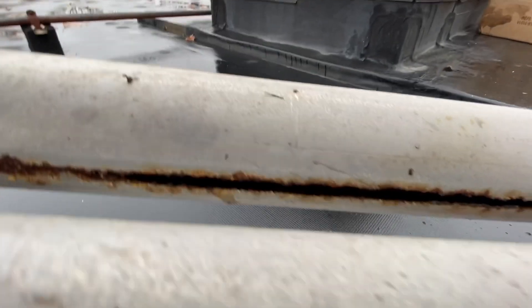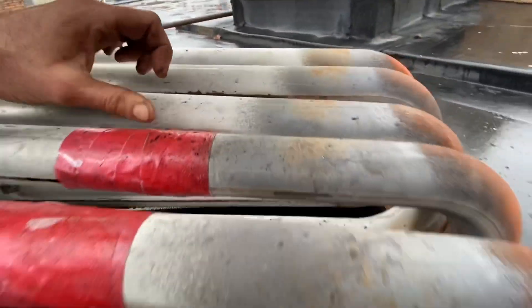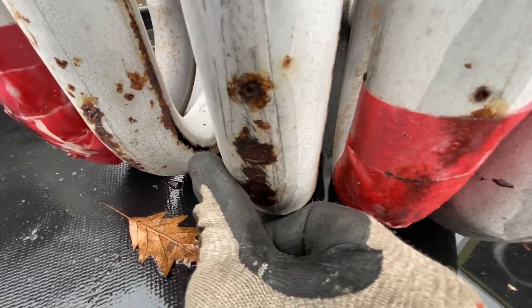You see that? That's right through — that's not even rust, that's just a hole. Whoosh. About to go. Tubes with little holes, down there, more cracks and seams.